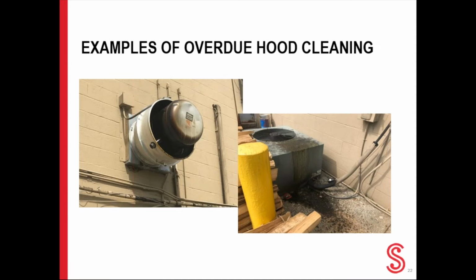The pictures above are some great examples of exhaust systems that are overdue for cleaning. In this instance, the hood system was servicing an open hearth wood fire grill. As you can see, the grease and creosote have begun dripping onto the heating and air unit that is located beneath the exhaust cap, making this well overdue for hood cleaning.